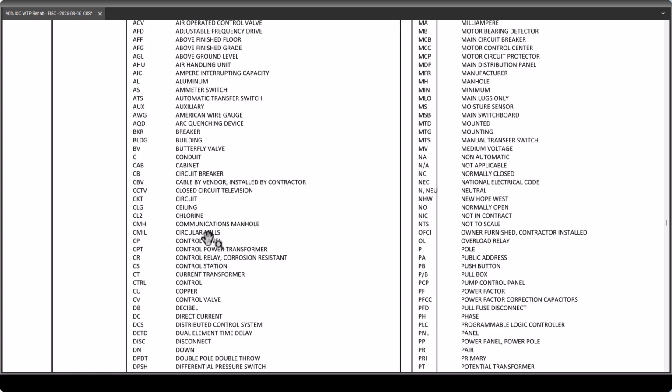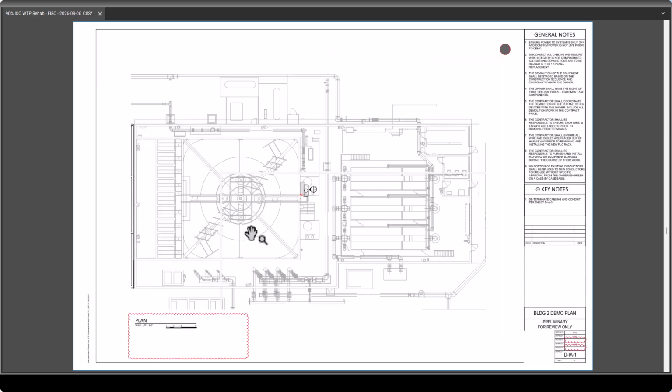People on YouTube, if you have abbreviations in your drawings, you have to have them here, or the contractor can say whatever he wants, and you have no leg to stand on. Okay. Yeah, that's a good note to have then. Yes. All right. So from an engineering perspective, I start here.